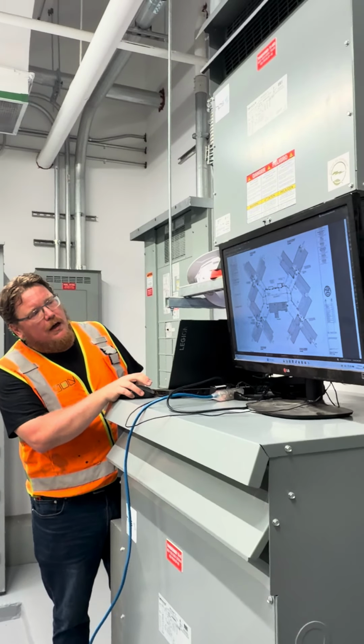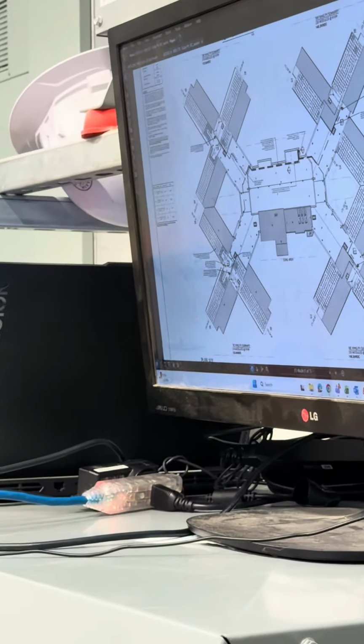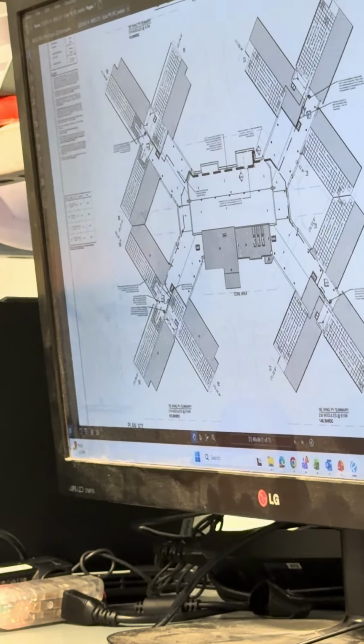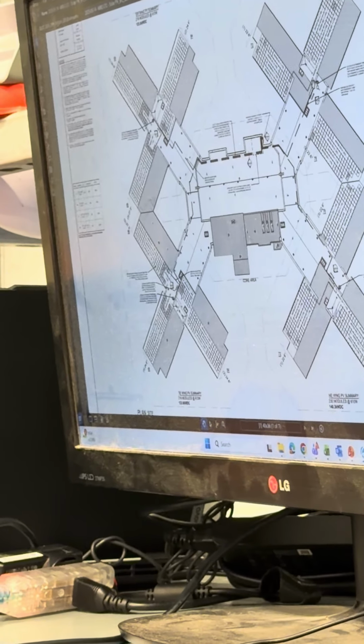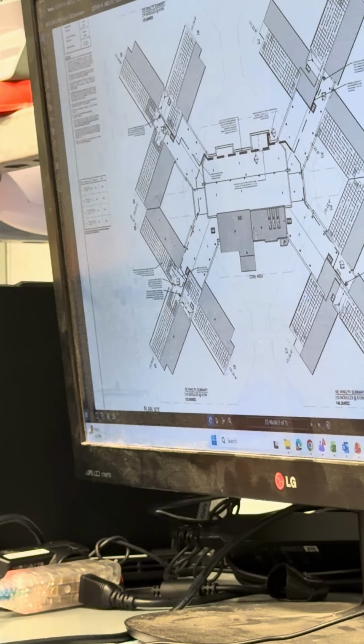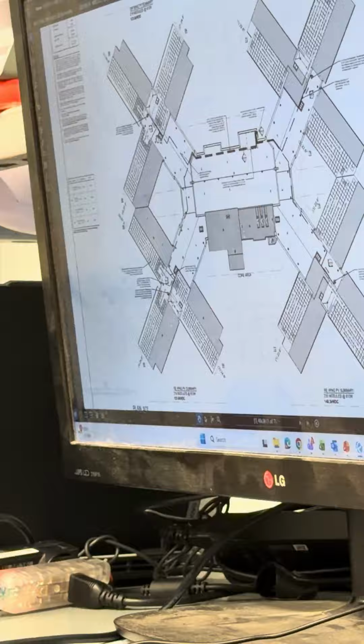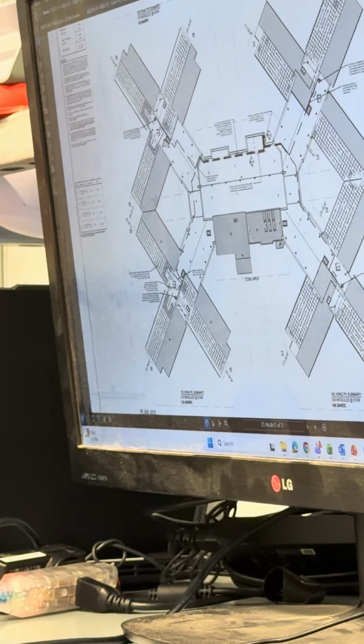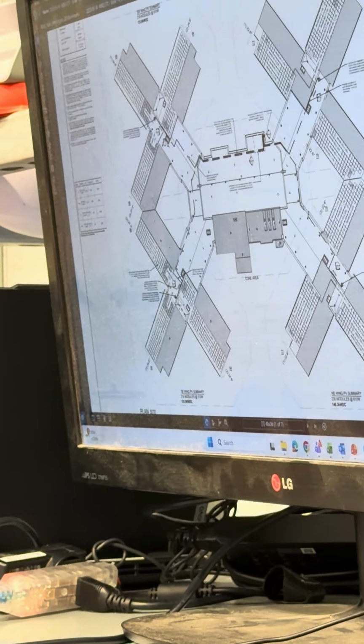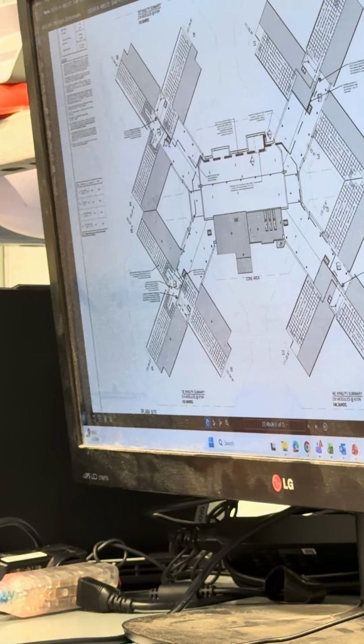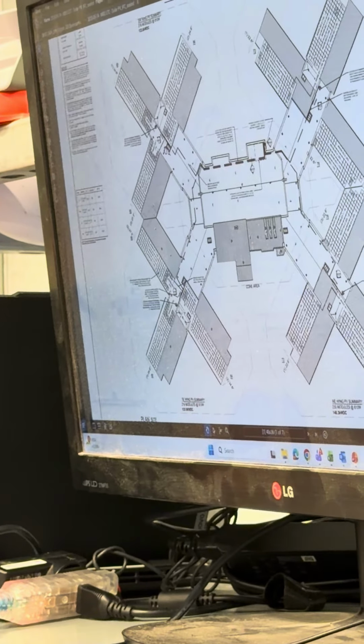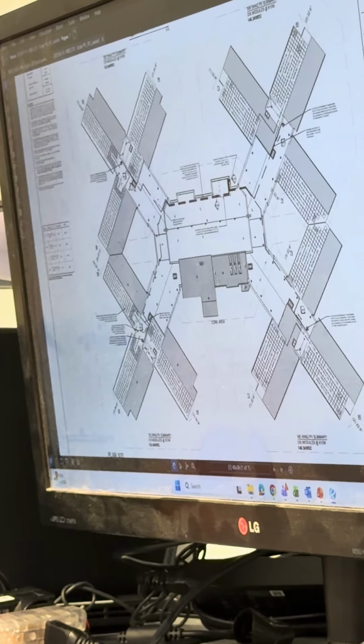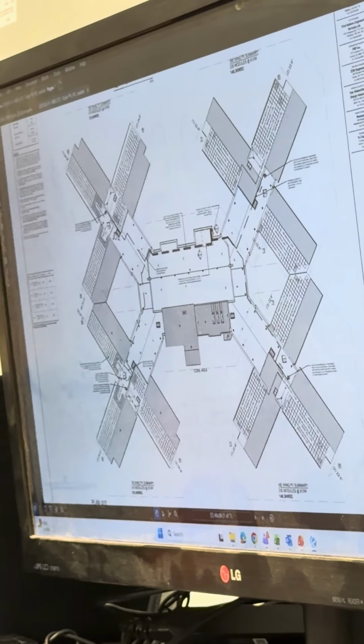On the flat roof portion — this is the flat roof part — there are 4 groupings of equipment, one at each wing. At each point there are 2 inverters, a transformer that steps it up to the 600 volts the building runs on, and some isolation disconnects. So there are 4 individual groups of inverters.